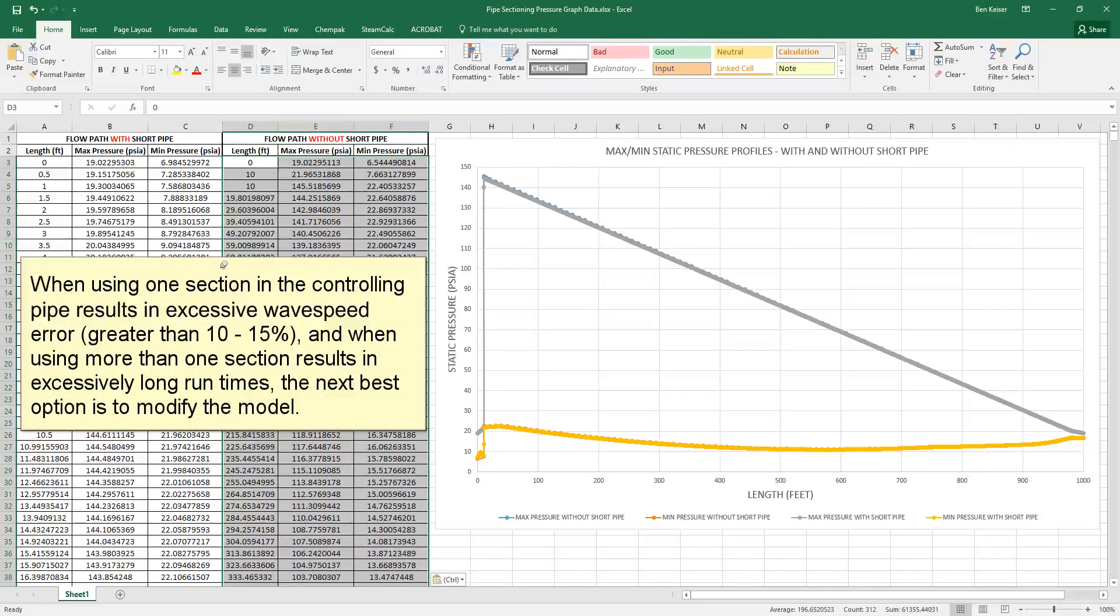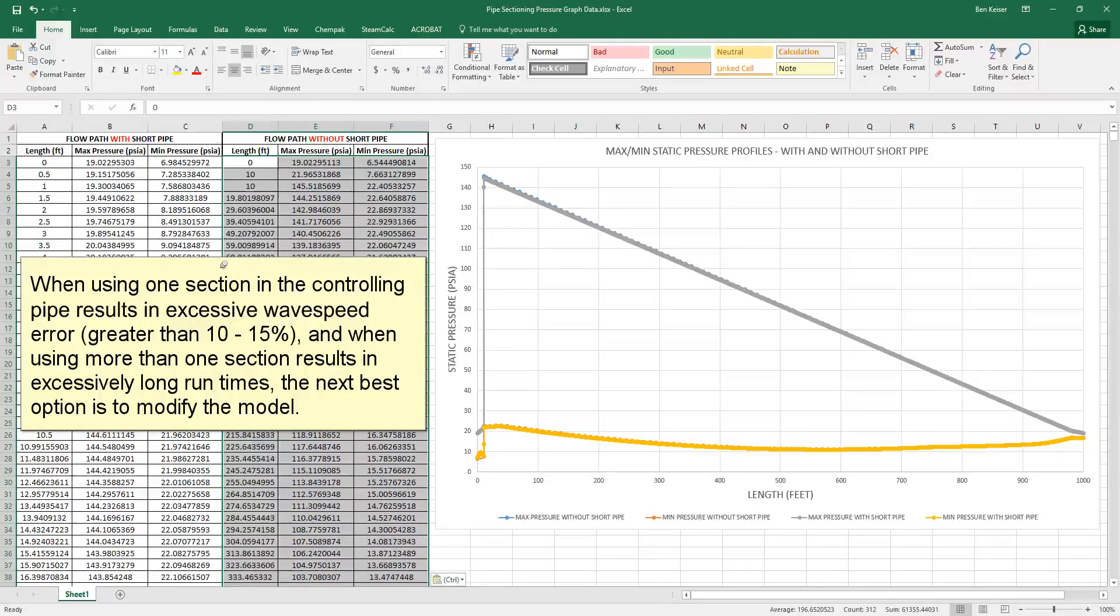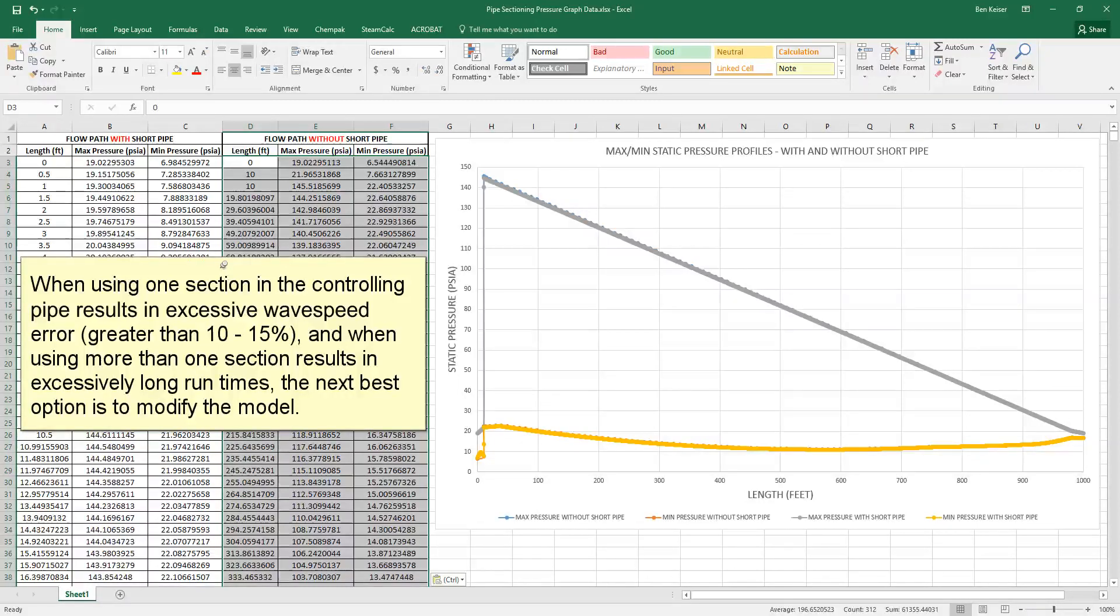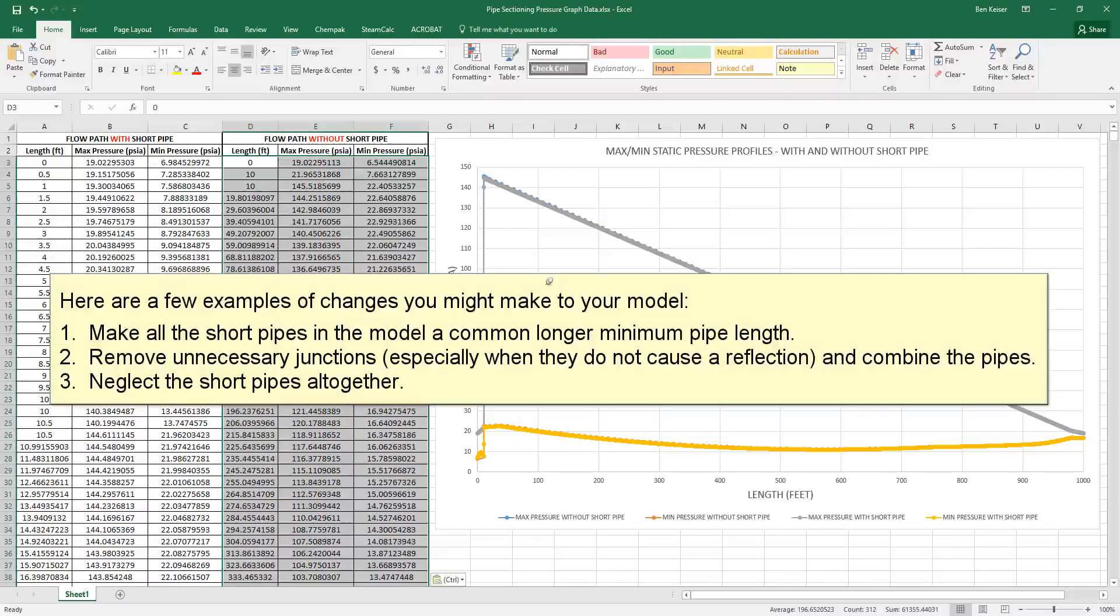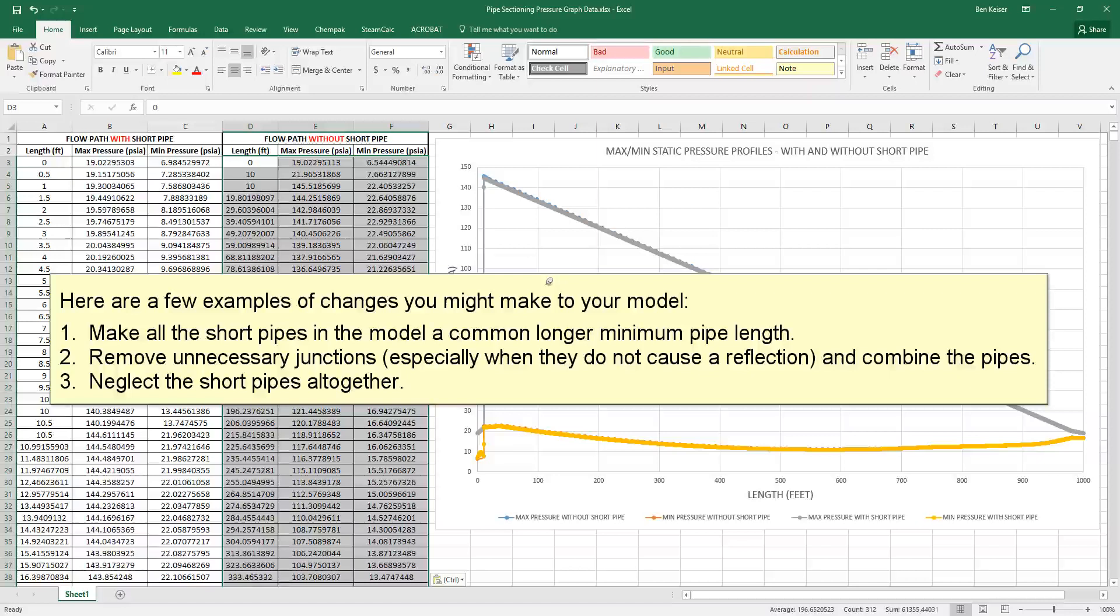When using one section in the controlling pipe results in excessive wave speed error greater than 10-15% and when using more than one section results in excessively long run times, the next best option is to modify the model. Here are a few examples of changes you might make to your model. 1. Make all the short pipes in the model a common longer minimum pipe length. 2. Remove unnecessary junctions especially when they do not cause a reflection and combine the pipes. 3. Neglect the short pipes altogether.